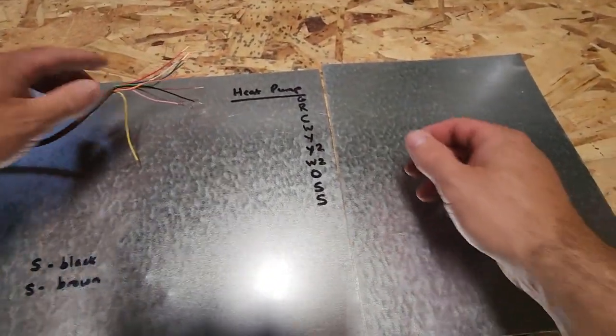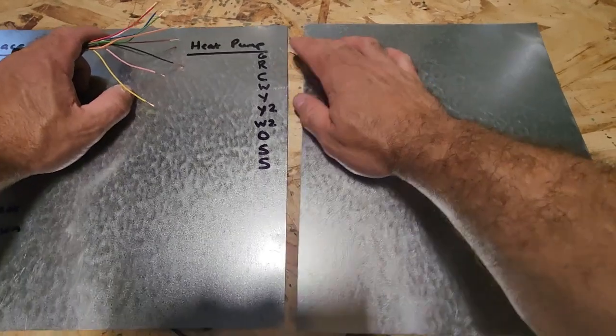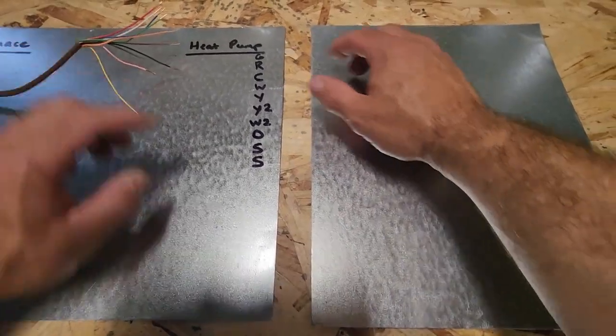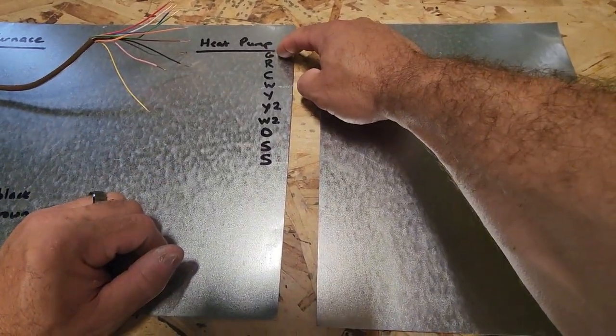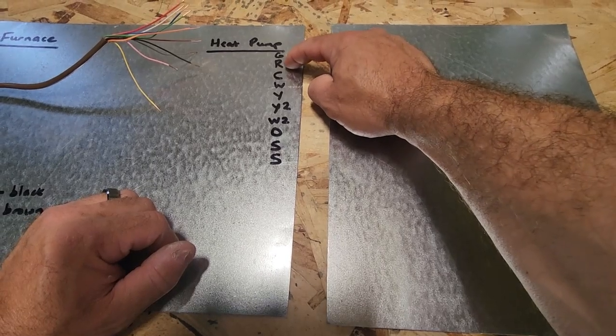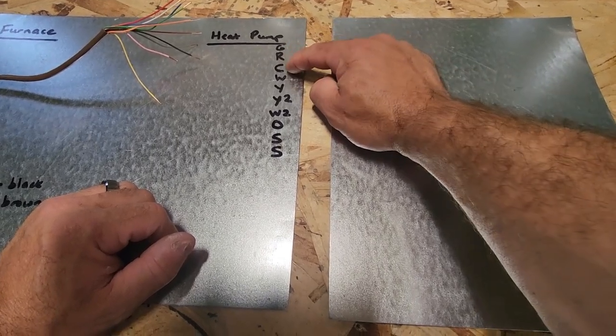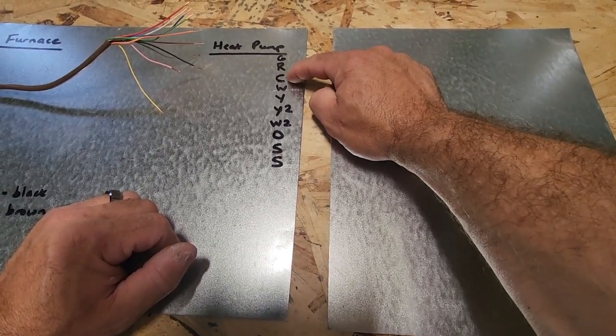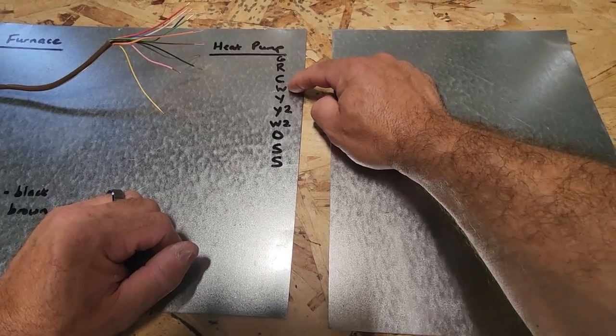So let's go over to if you had a heat pump that you were going to wire. So these ones are all going to be the same except for a couple different things, okay? So you're going to have your green for your fan, G, your 24 volts hot, red, your 24 volts common, blue. Now this is where it's different.